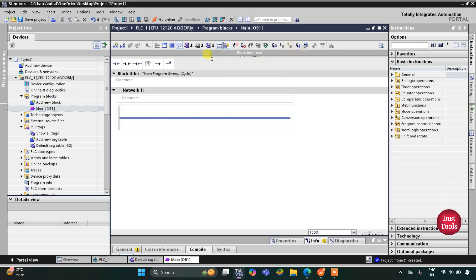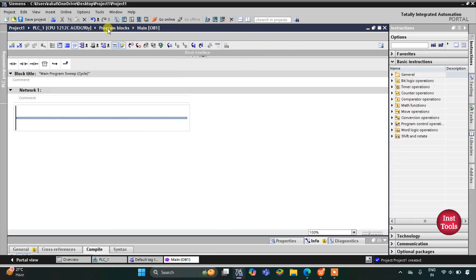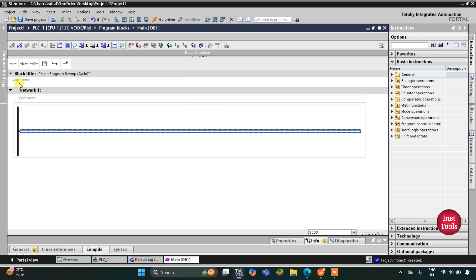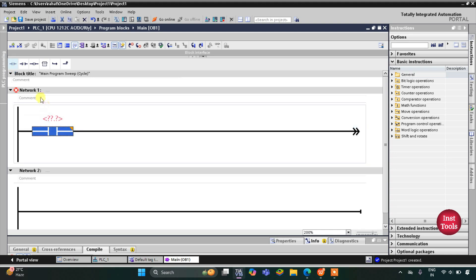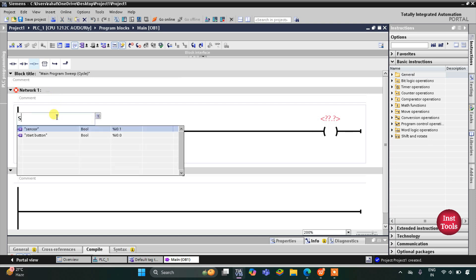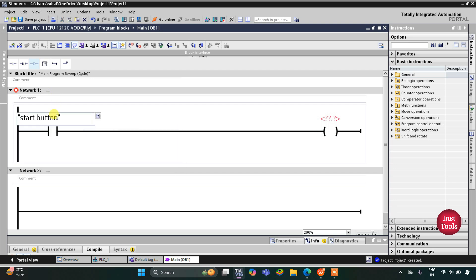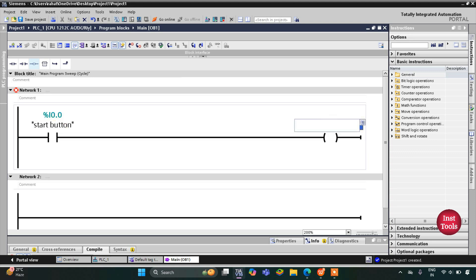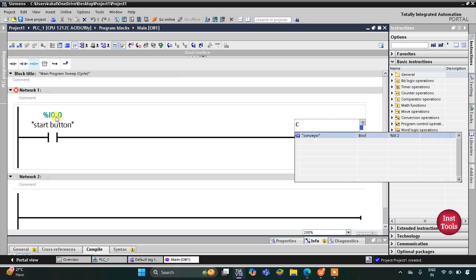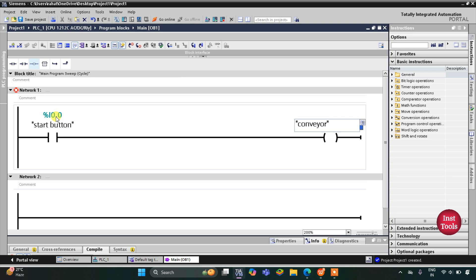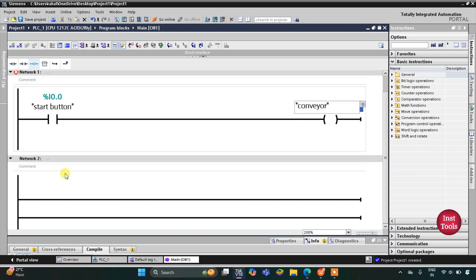Here we will be drawing the ladder diagram. First I will zoom in, and then I will insert a normally open contact for the start button and then a coil for the conveyor. So this will be the start button and it will be connected to the conveyor coil. When the start button is turned on, the conveyor will start.